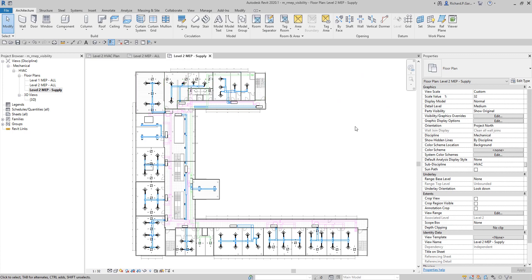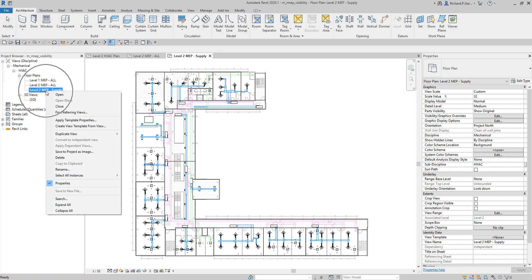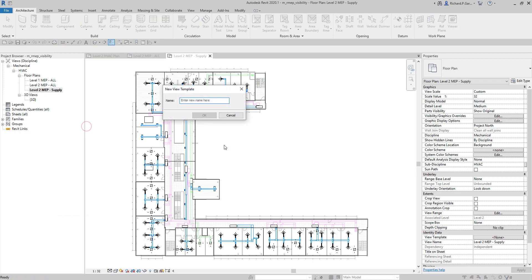Now that we've set up the Level 2 MEP Supply view, we're going to use it to create a view template - the standard workflow is to set up your view first, then create the template. To create a view template from this view, right-click Level 2 MEP Supply in the project browser, select 'Create View Template from View', and give it a name - let's call it 'MEP Supply'.